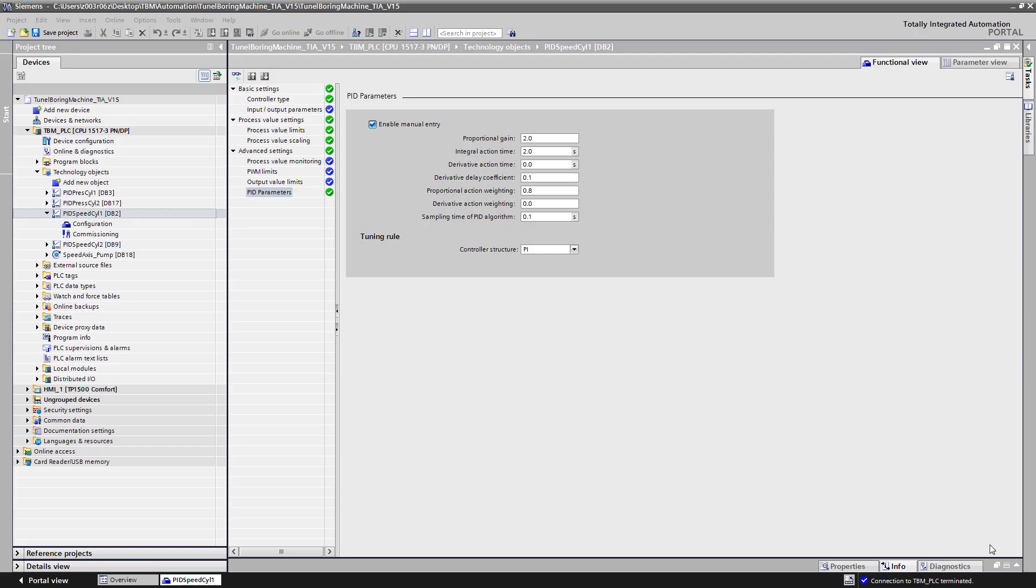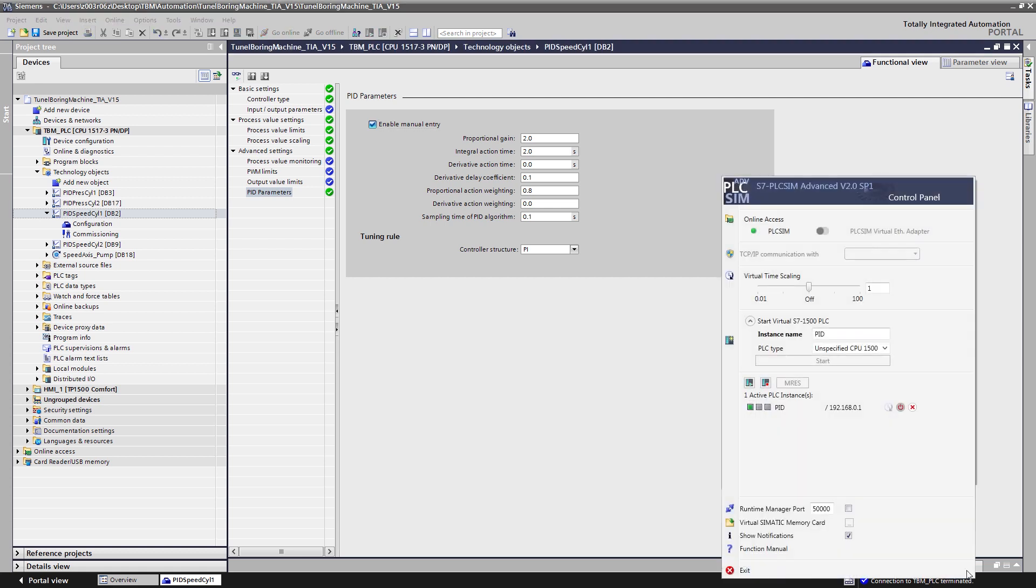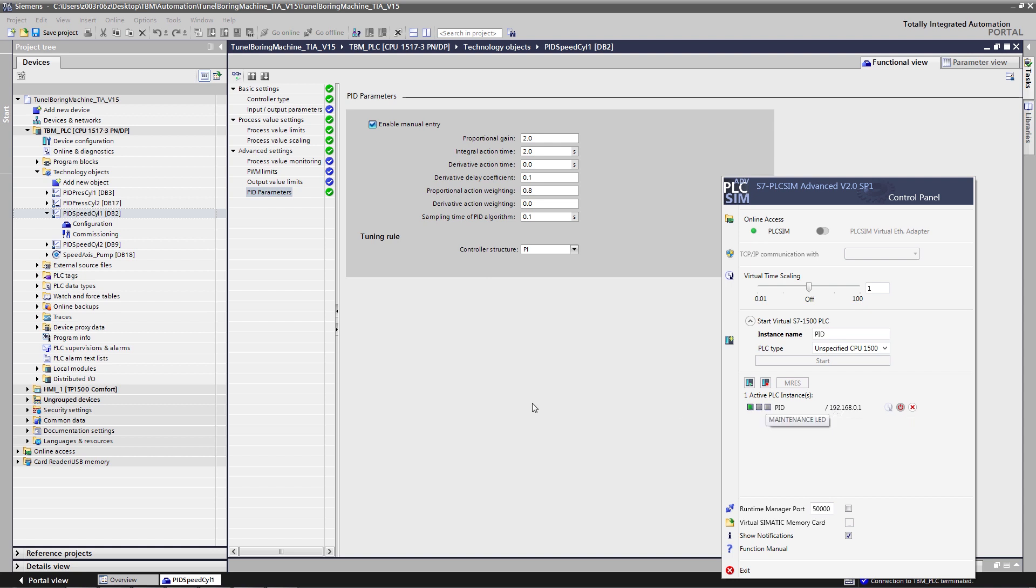We have configured a PI controller in TIA Portal to regulate this valve. We have downloaded this code to PLCSIM Advanced, our virtual controller for the SIMATIC S7-1500 series. The CPU is already in run mode.